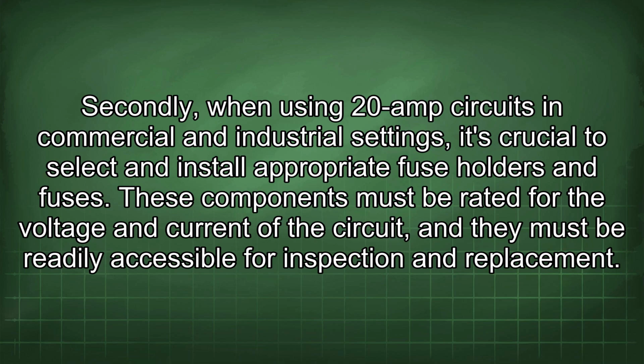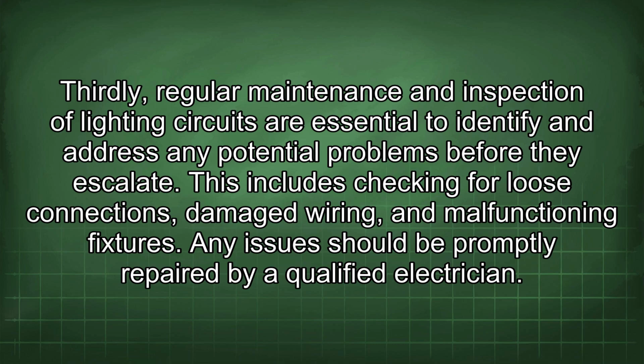Secondly, when using 20 amp circuits in commercial and industrial settings, it's crucial to select and install appropriate fuse holders and fuses. These components must be rated for the voltage and current of the circuit, and they must be readily accessible for inspection and replacement. Thirdly, regular maintenance and inspection of lighting circuits are essential to identify and address any potential problems before they escalate. This includes checking for loose connections, damaged wiring, and malfunctioning fixtures. Any issue should be promptly repaired by a qualified electrician.